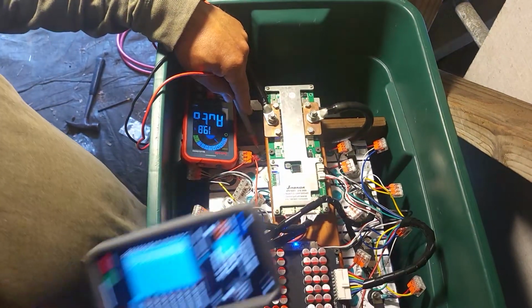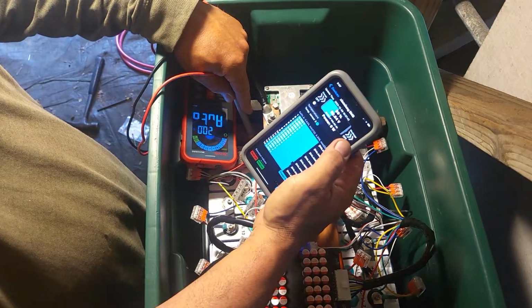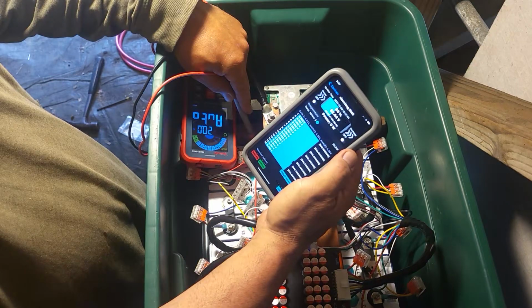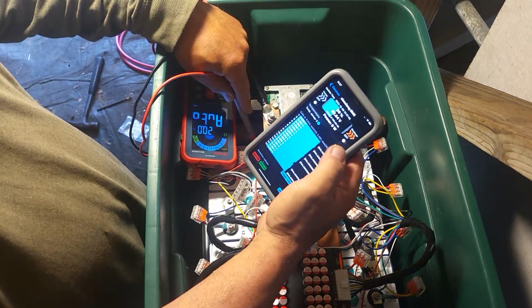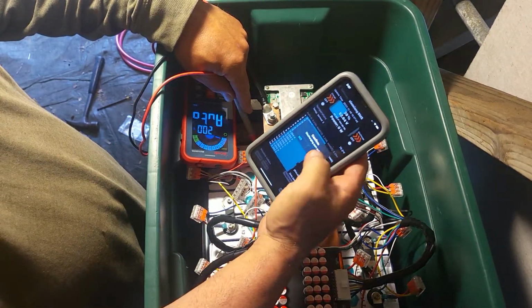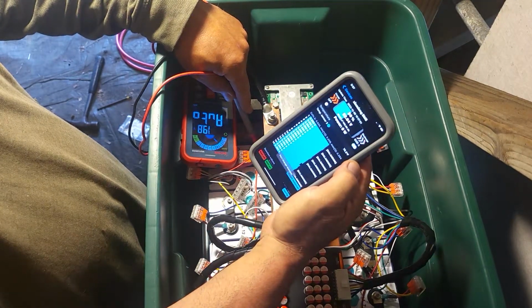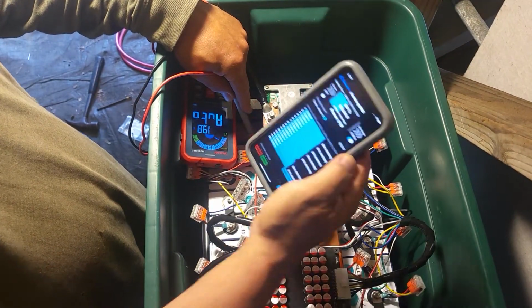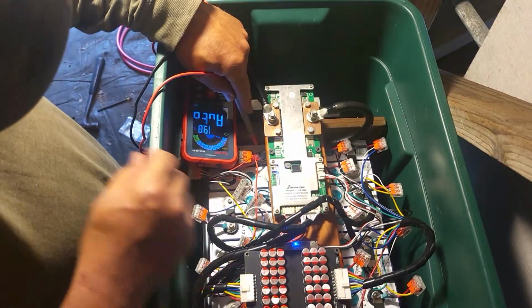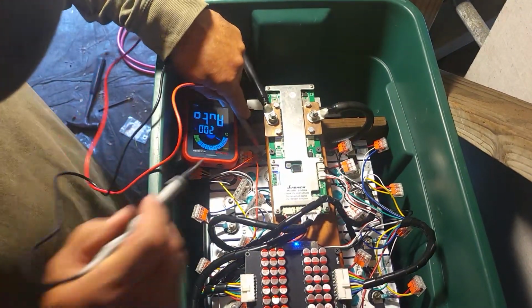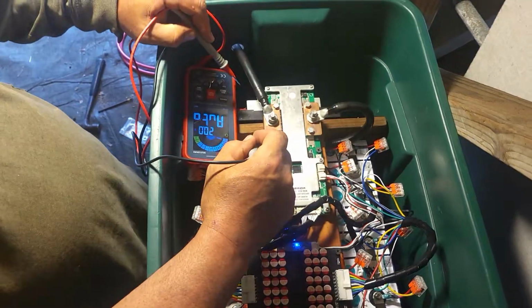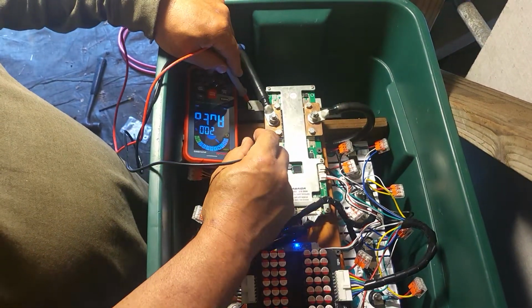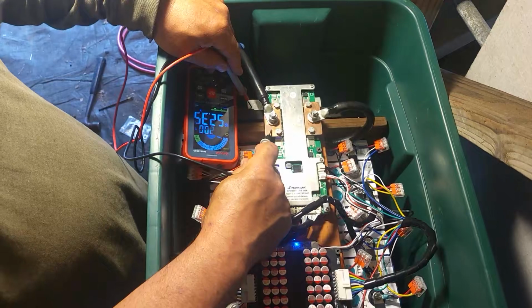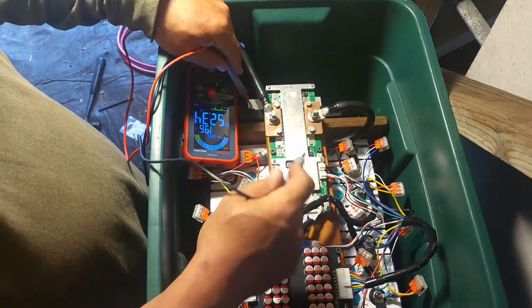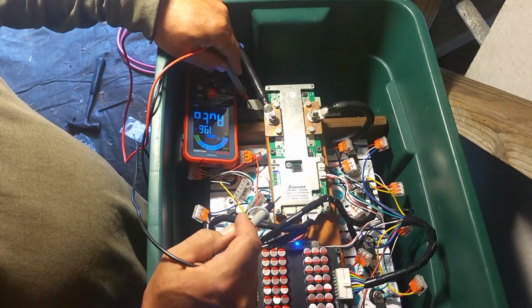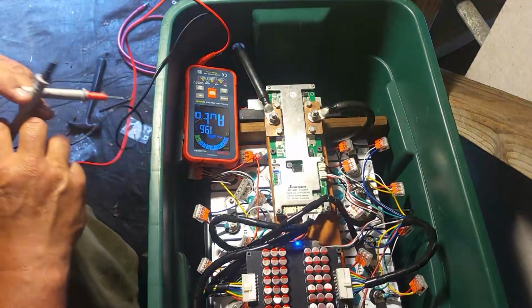So if I come back to this app and turn the discharge switch to on, discharging port on, yes, okay it's on. Now I should be getting a reading from the positive to the negative here of 50. Yeah, so I got full. That's telling me the switch for the BMS is working properly, so we're good there.